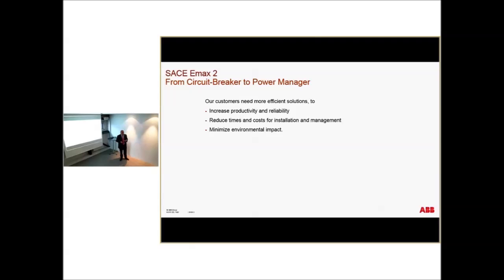Minimize environmental impact. It's important now with new regulation to have something that is completely recyclable. And in some markets, I know the consumption is not very high, but the power losses need to be as low as possible. So it has to do tough work, not only working on protection, measurements and characteristics, but also reducing the consumption of the breaker when it's permanently installed. Because if you reckon 1 watt over the life of a breaker, at the end it is a cost.